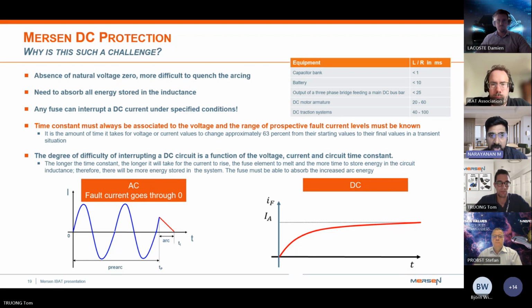Also, the degree of difficulty in interrupting a DC circuit is a function of voltage, current, and the circuit time constant. We need to know all these parameters to properly size the right fuse. Another important factor is the minimum current, or smallest current, that the fuse has to open for - a crucial factor when selecting a DC fuse. So this covers the importance of DC and what Mersen specializes in with DC fuses.